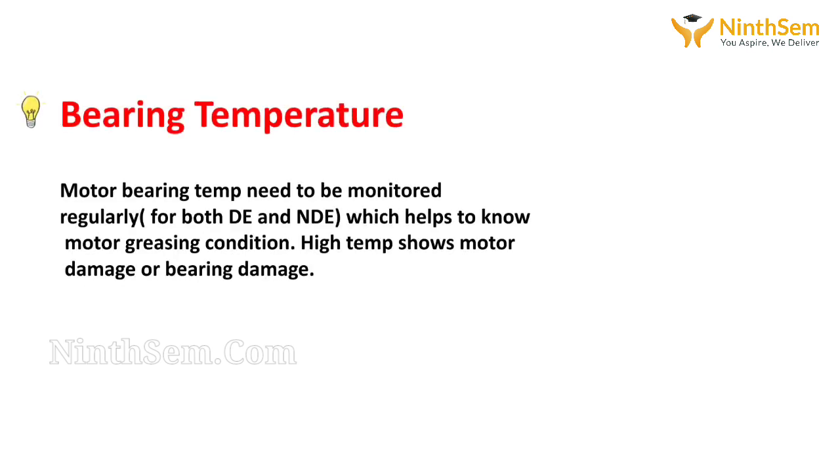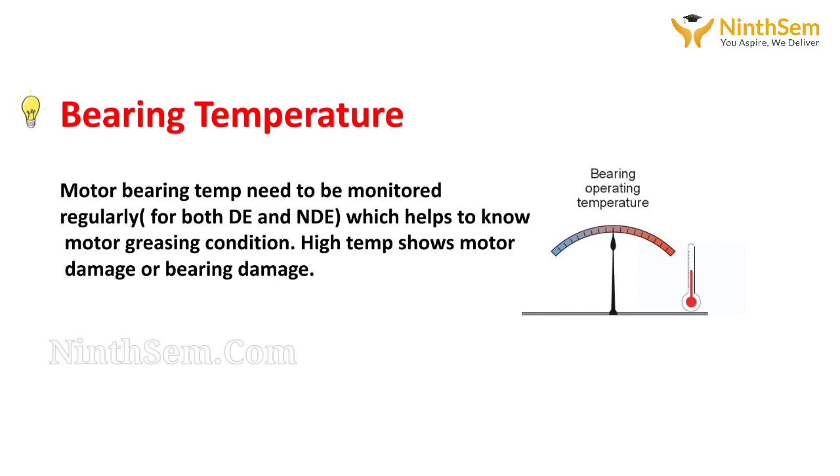The next parameter is bearing temperature. Motor bearing temperature need to be monitored regularly for both drive end and non-drive end of motor, which helps to know motor greasing condition. High temperature shows motor damage or bearing damage.